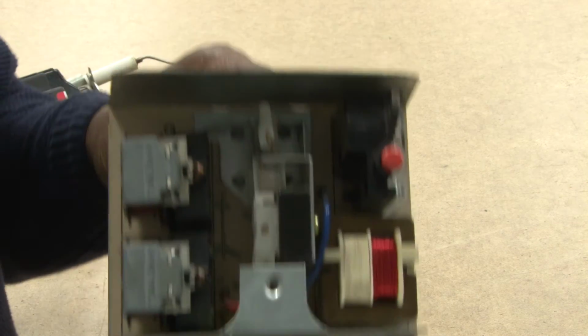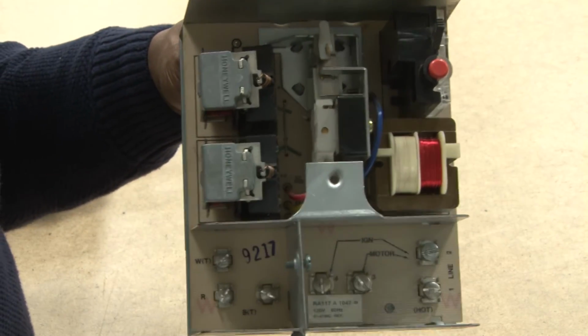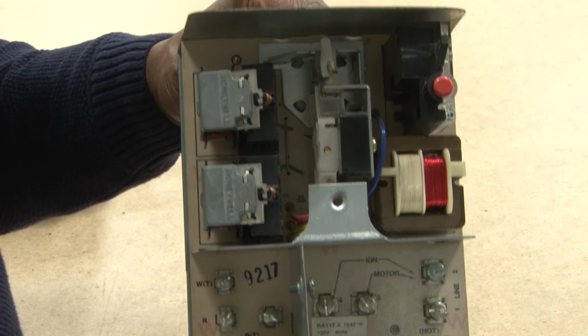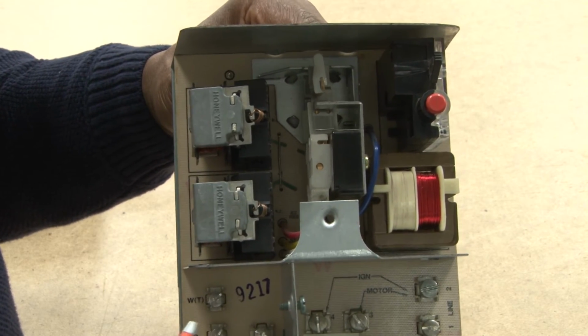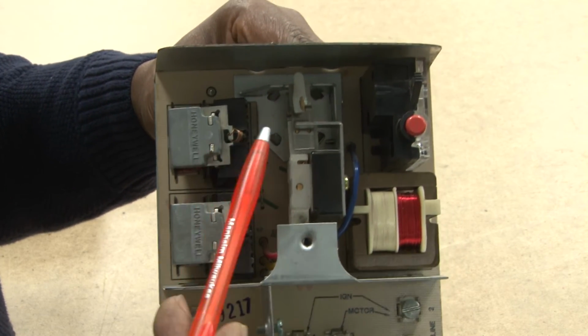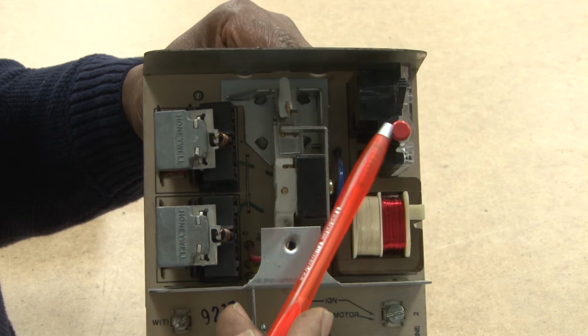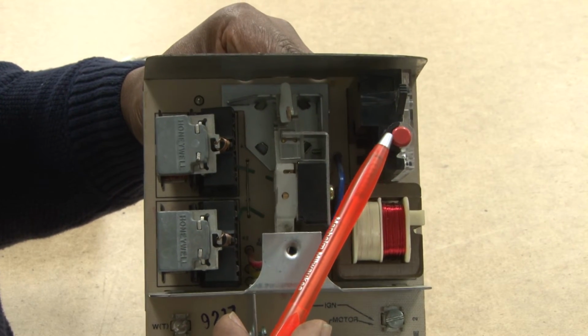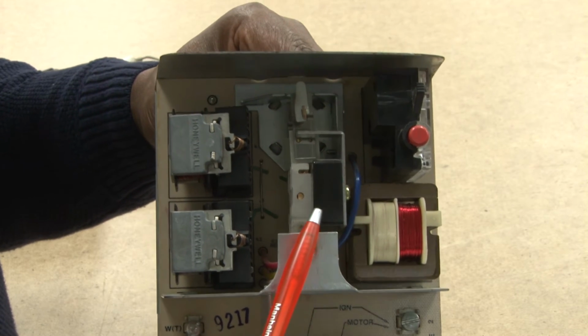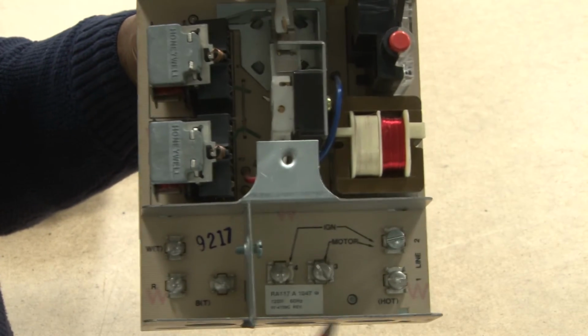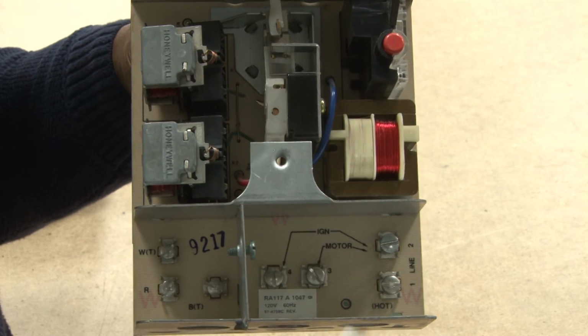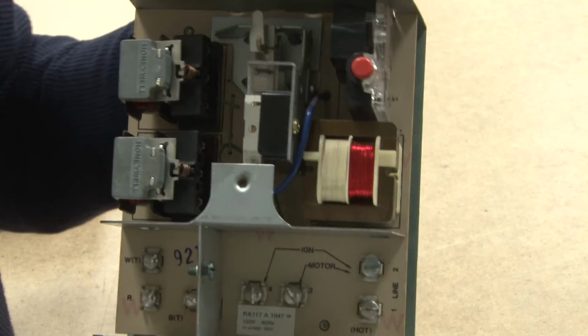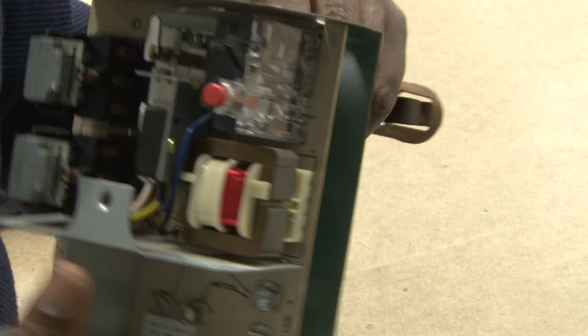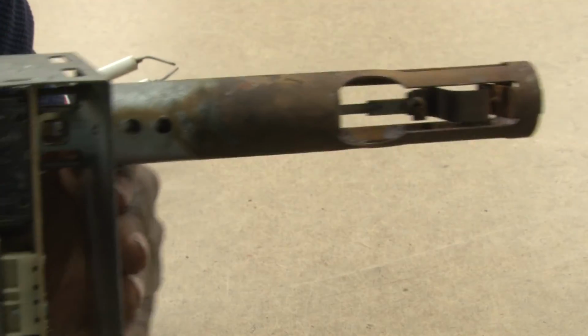Another device we're going to show is an old style primary control. This was the safety control they used on old oil furnaces to control the operation of the oil burner. Basically, it had relays inside of it, and a safety switch you can reset if it didn't light within a certain amount of time. And of course, the thermostat wires went to it, and all the wiring for the burners will also be connected to this. But how it sensed the flame is that the old style used the heat temperature in the stack.